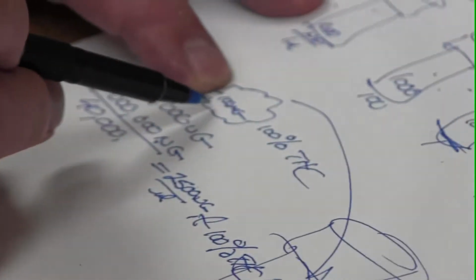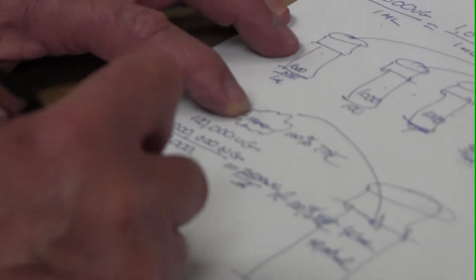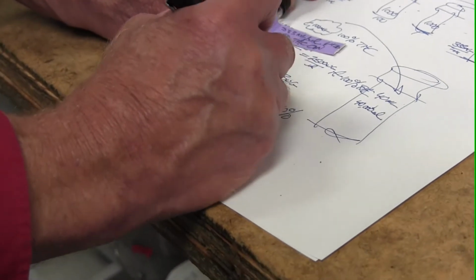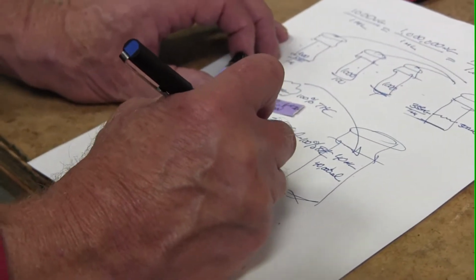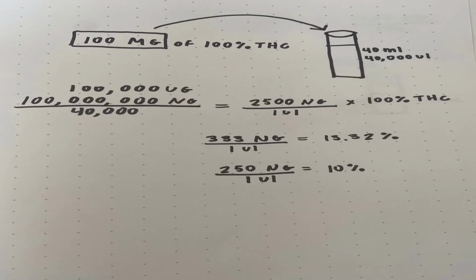And that's if it's 100% THC. So imagine if it was 10% THC. It's easy to do the math in your head. 10% THC would correlate to 250 nanograms per microliter. That would be the equivalent of starting out with 100 milligrams of 10% THC. But we injected what's on our calibration standard bottle, which says 333 nanograms per microliter, and that's somewhere between 2,500 and 250, somewhere in here. So 333 nanograms per microliter works out to 13.32%.